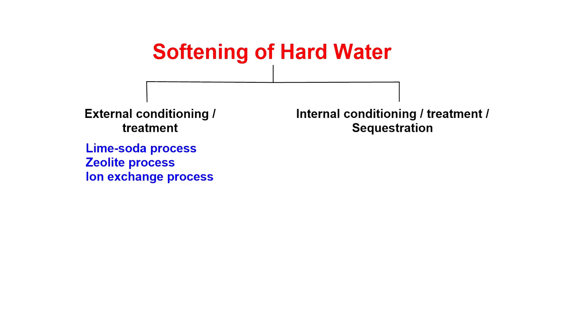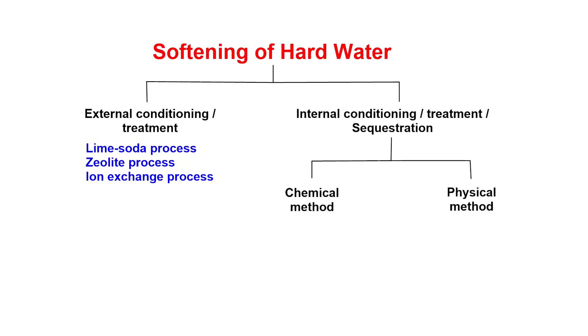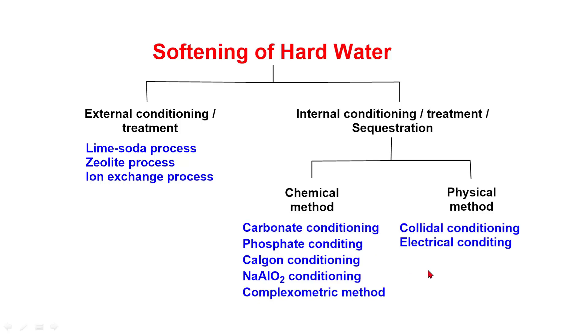External conditioning methods are: lime soda process, zeolite process, and ion exchange process. Internal conditioning involves chemical methods and physical methods. Chemical methods include carbonate conditioning, phosphate conditioning, calgon conditioning, sodium aluminate conditioning, and complexometric method. Physical methods include colloidal conditioning and electrical conditioning.